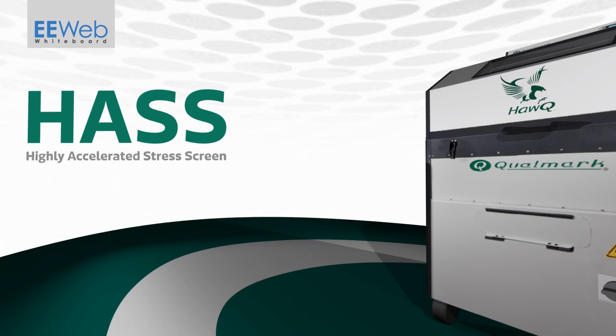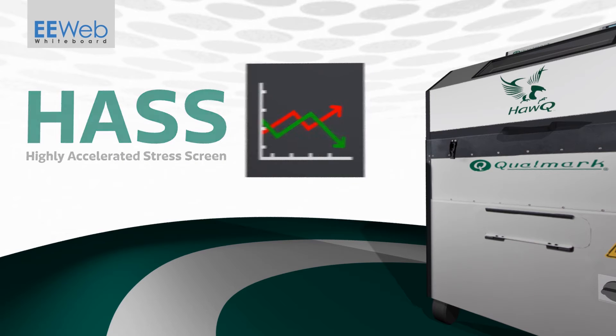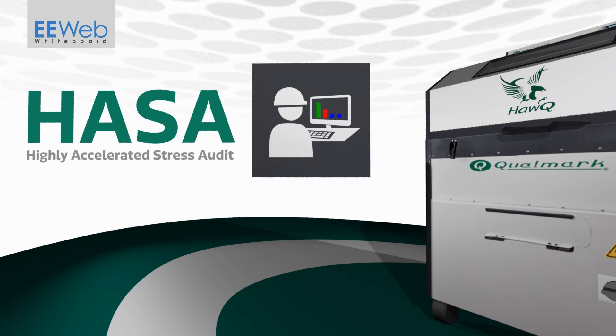HASS, highly accelerated stress screen, discovers latent production flaws by stressing a product beyond specification but within the product's design operating margins, determined by HALT testing. HASA, highly accelerated stress audit, is a form of HASS that uses a sampling plan for high volume production. Both HASS and HASA are used to verify that any process shifts that may impact product reliability at the customer are captured.